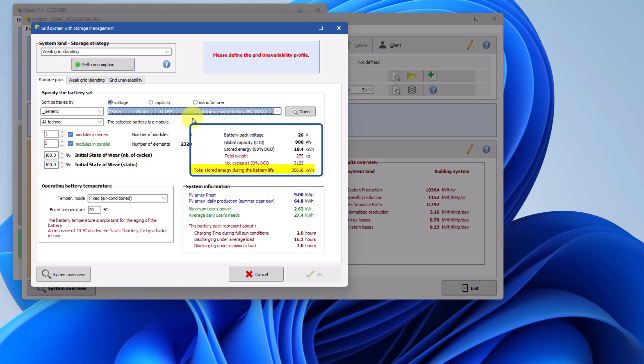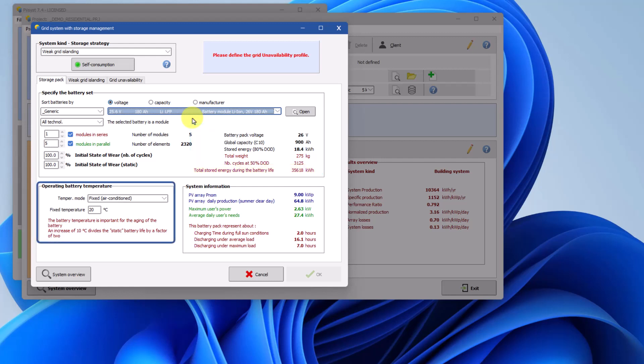Additionally, you can determine the total energy that can be stored over the battery's lifetime. In the bottom left box, you can choose the battery's operating temperature, which is used in the battery's aging model. A 10-degree increase in the operating temperature reduces the battery's statistical lifetime by half.